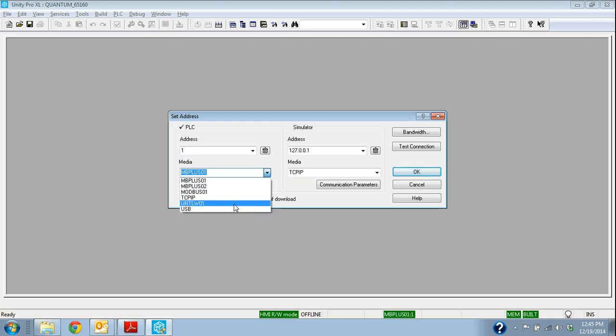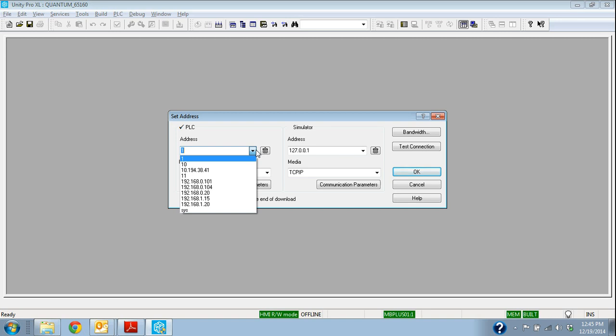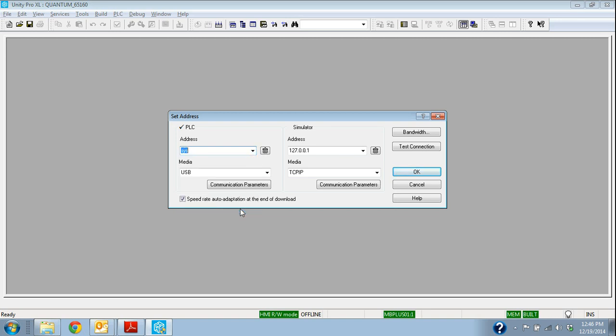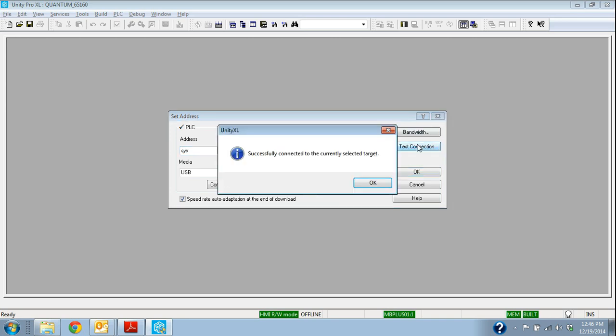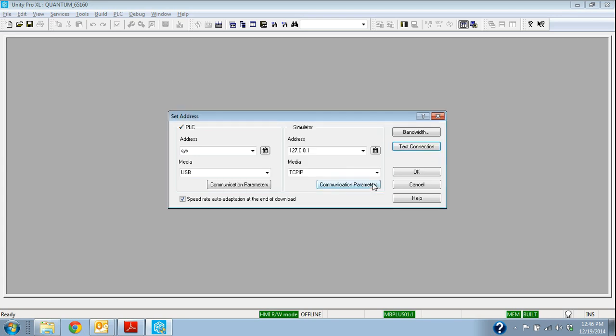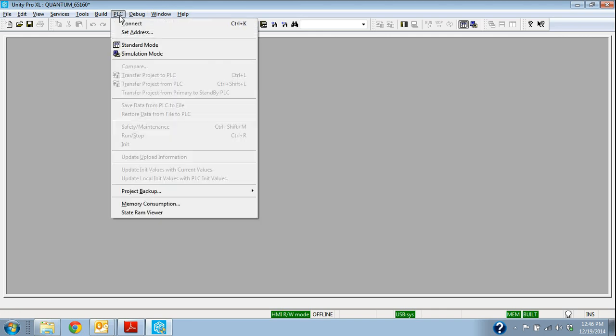So I need to change this to USB. And in this case, the default address when we use the USB on the Unity controllers is Sys, S-Y-S. So I set those. I set USB, I set it to Sys, and then this is important. I have this test connection box. If I don't get a good response back from this test connection, then I might as well forget trying to load the project onto the controller. So I always want to make sure I have a successful connection here. So I hit the test connection, and we can see that it came back successfully connected to current selected target. So that's the controller out of the box with the default address. So I say, okay, that's the one I want to use. We can see down here at the bottom it's changed to USB Sys.